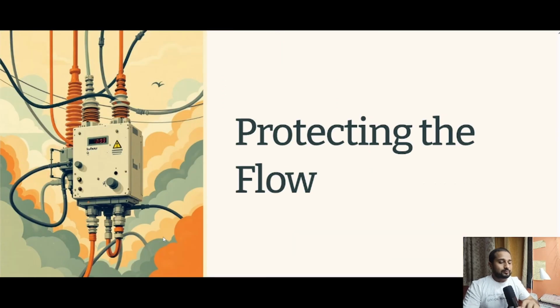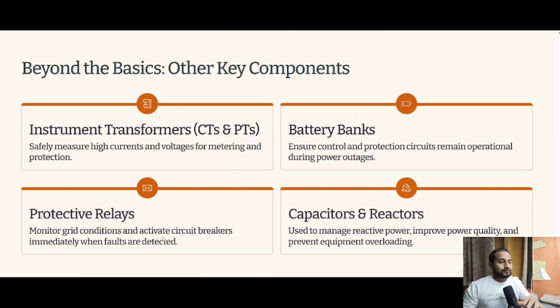Then how to protect the flow of energy? The flow of energy is protected by the following equipment. They are instrument transformers such as current transformers or potential transformers. They safely measure high currents and voltages for metering and protection purpose. Now this current and voltage measurement is supplied to the protective relays which monitor grid conditions and activate circuit breakers immediately when the faults are detected.